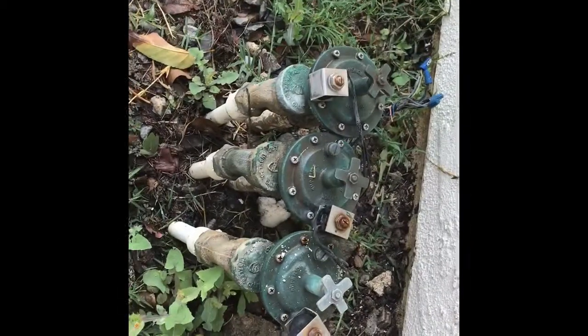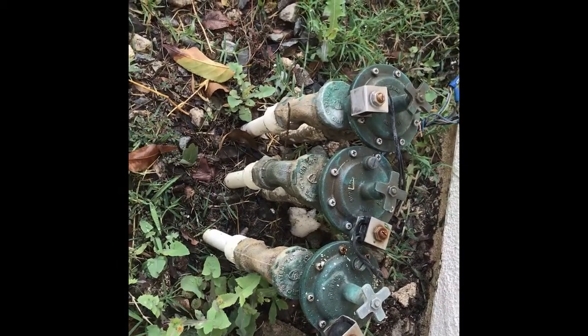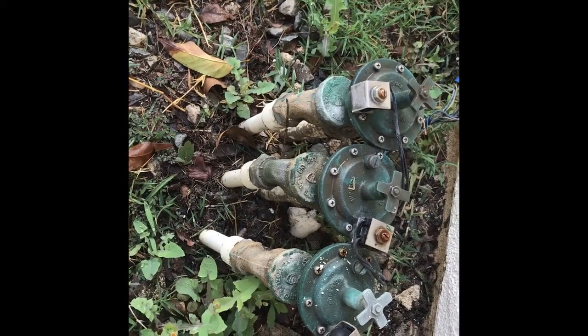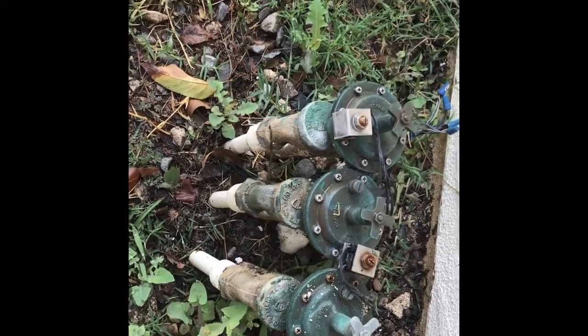This is a little unusual case. We've got sprinkler heads here — when I arrived and the other inspector arrived, they were shooting water all over the place willy-nilly. I shut off the water to the house in order to solve this problem. Many of them have a means of shutting them off in the interim, but these did not.